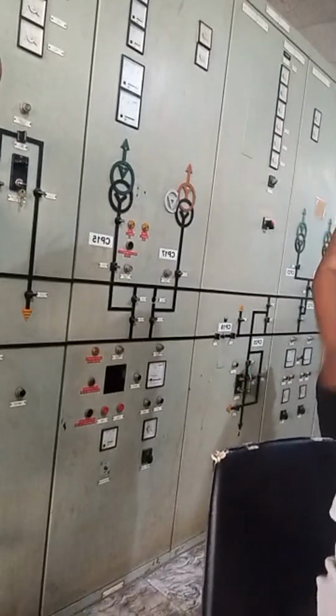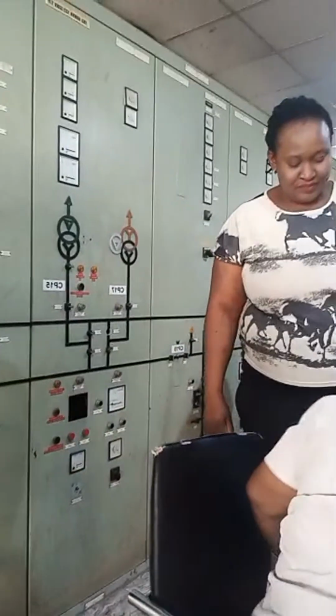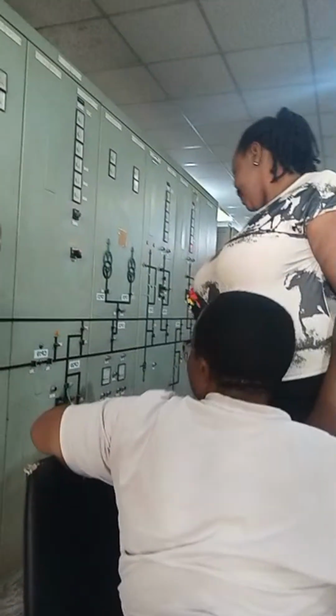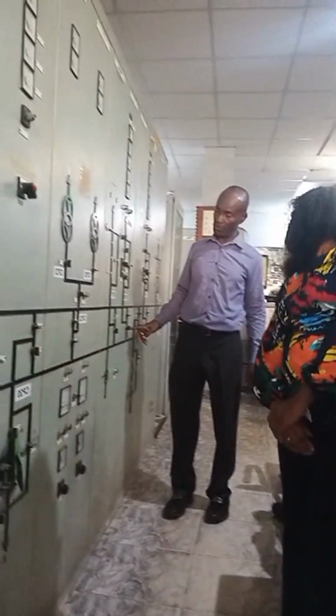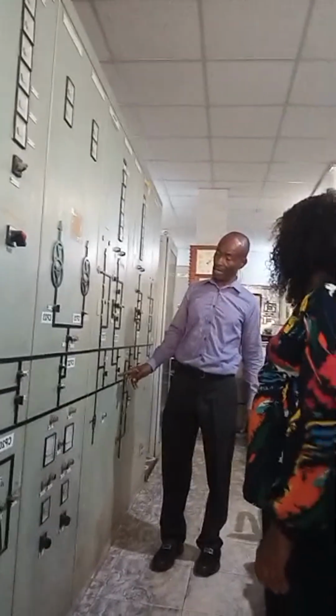This is a double bus bar breaker system, do you understand? Each of these, just connected, look at it. This is an isolator, this is an isolator, do you understand? This one is in the close position, telling you that this equipment is receiving supply from bus one. This one will go to bus one, is that correct? And what is this line?